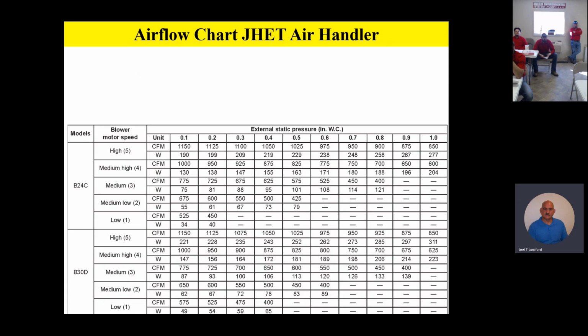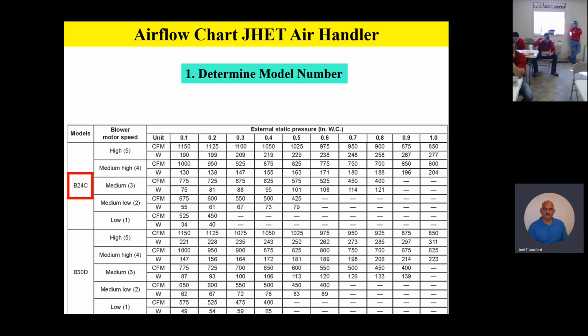So go ahead and grab your airflow chart that says JHET. You're going to notice these airflow charts all have the same type of look and feel and theme. Step number one, you determine what model of air handler you're looking at. Step number two, you determine what speed tap you're on that motor. Once you determine the model and the speed tap, you actually look at the speed tap and see what speed tap you're on.